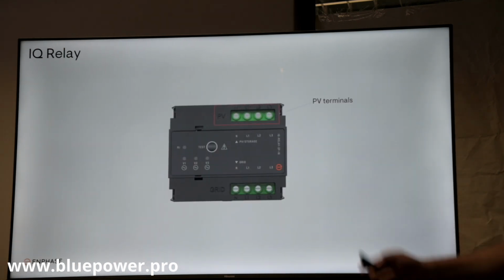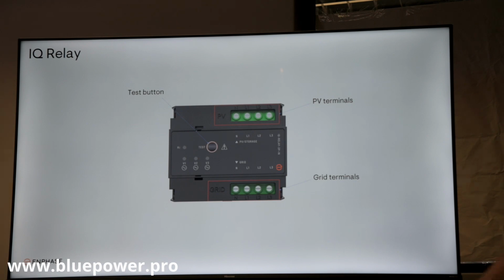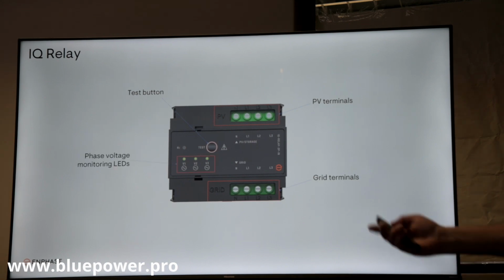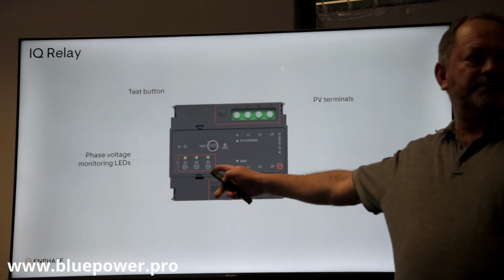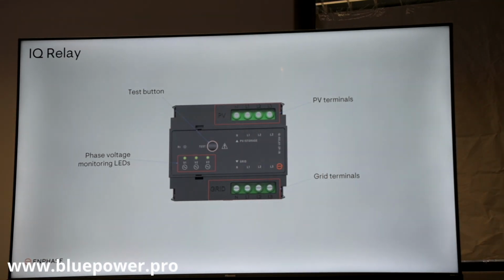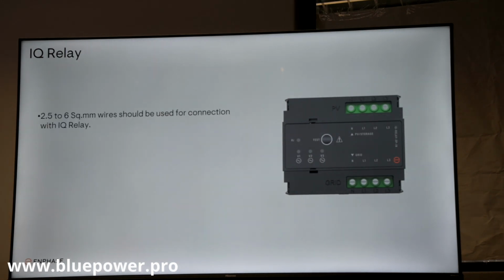So, as I said, there are the PV terminals and the grid terminals. Then there's the test button, which you use to identify L1, L2, L3 if you want one of them to not be in circuit. Then you've got your phase voltage monitoring LEDs. When I used to be out in the West, we used to have a lot of pumps that burned out because one of the phases fell away. So this will monitor, and it will show you when one phase falls away, and it will disconnect. It will protect your equipment, so you don't get any damage. And then obviously, as I said, there's also the frequency LED.